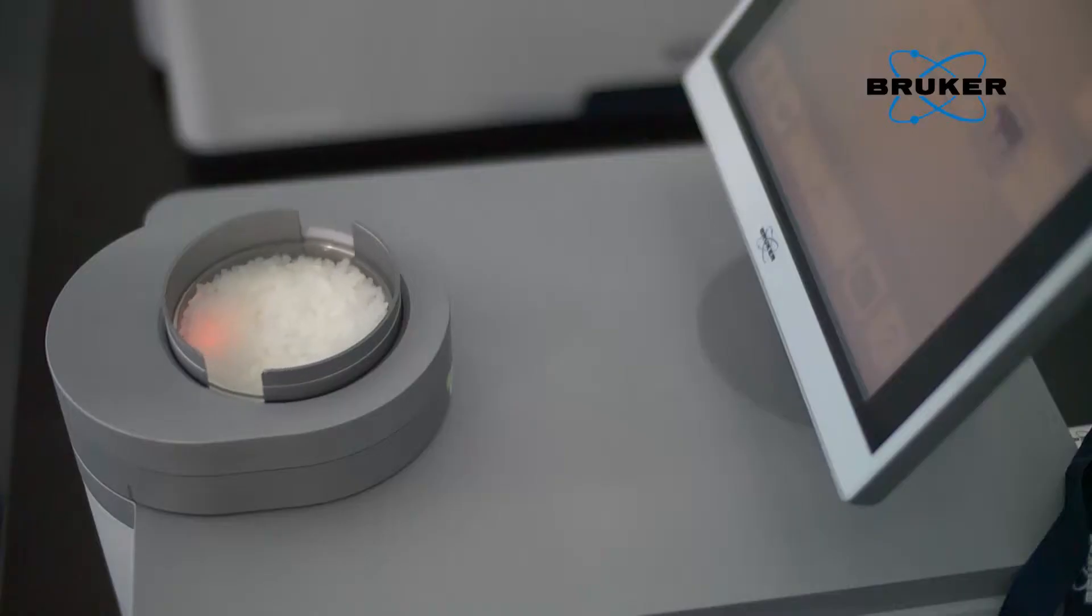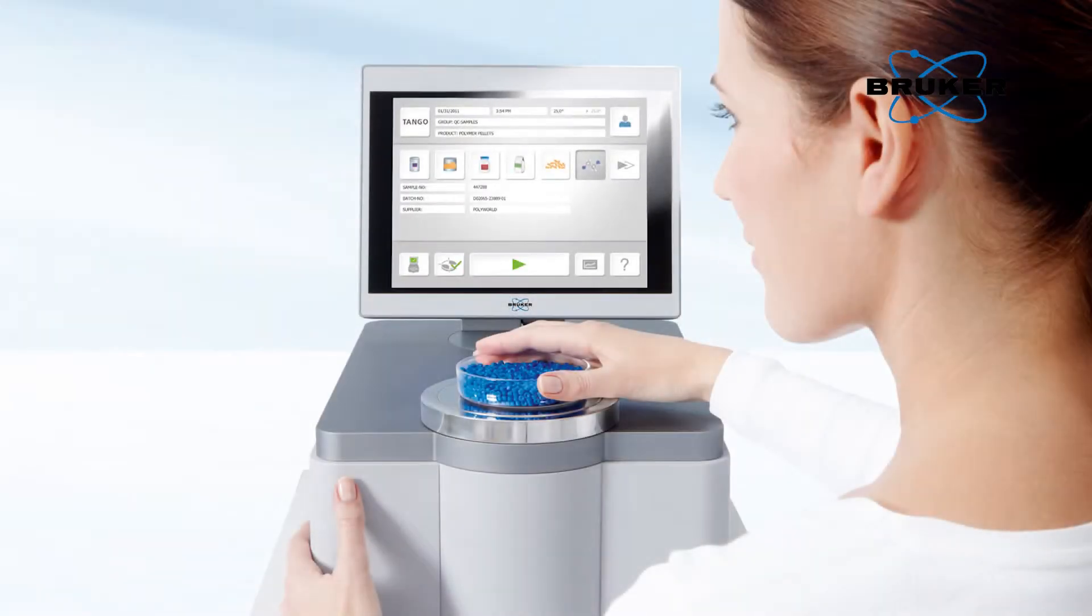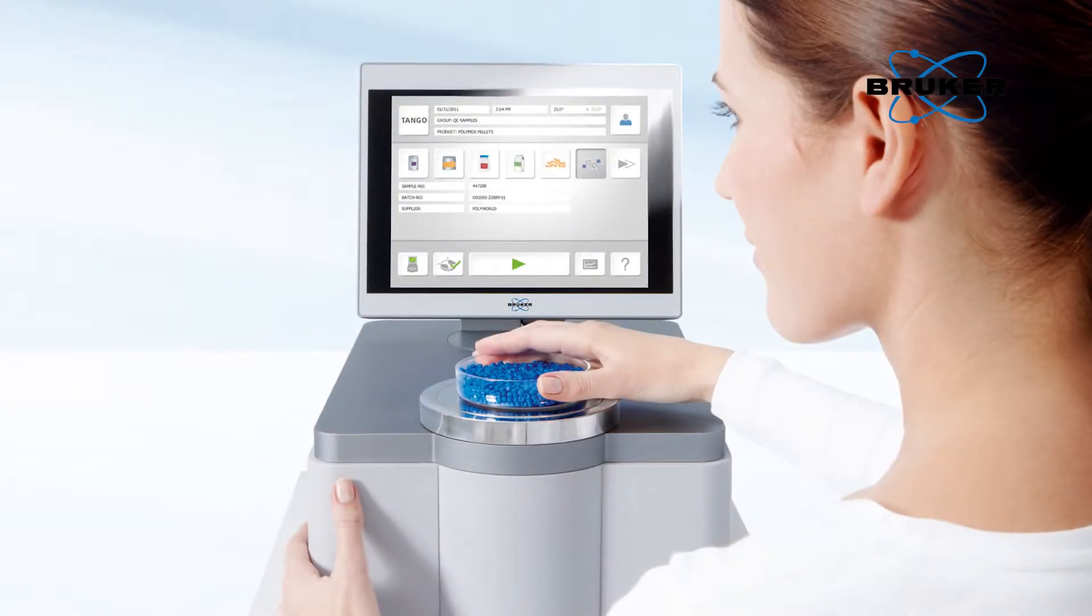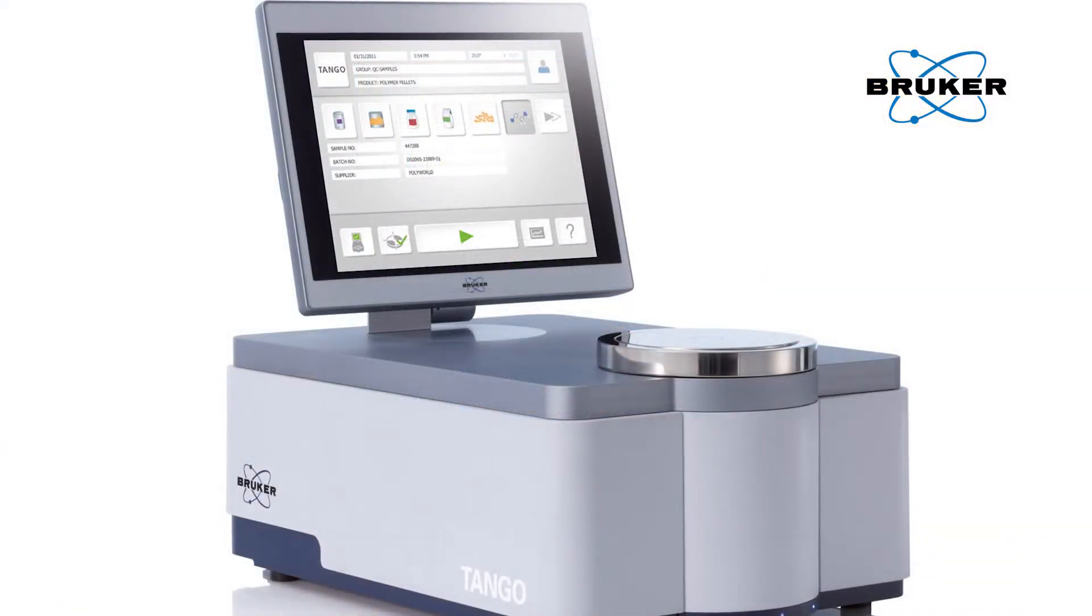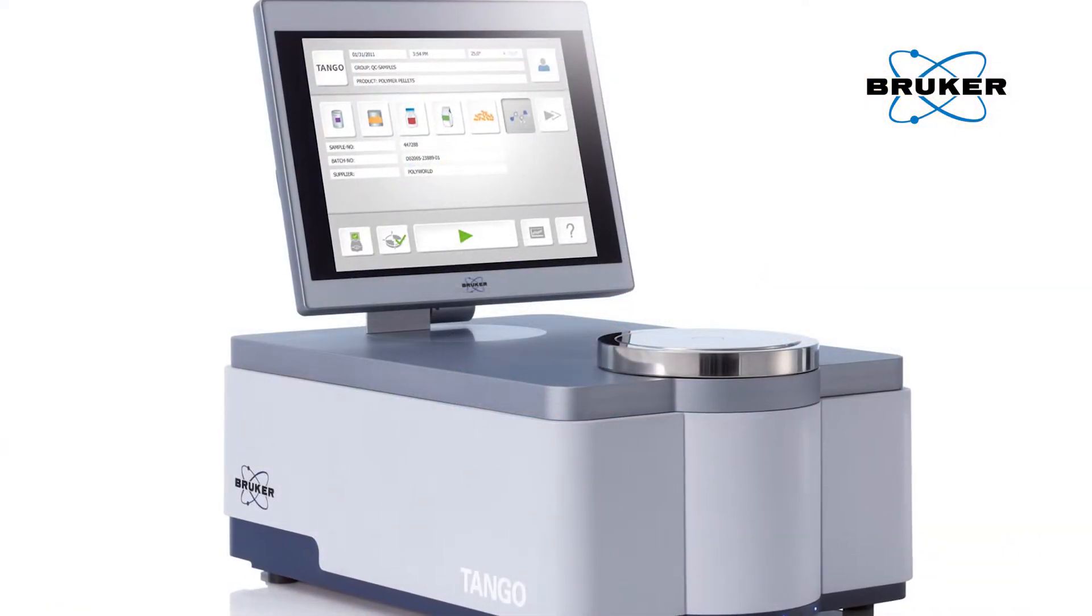In addition, you also have the calibrations that you develop for that particular material. The methods or the calibrations that you have on the Tango can be qualitative or quantitative or both. This is a big advantage of the Tango software, allowing for multi-evaluation predictions. The calibrations can be set up to identify your materials as well as give multiple component evaluation all from the same scan.